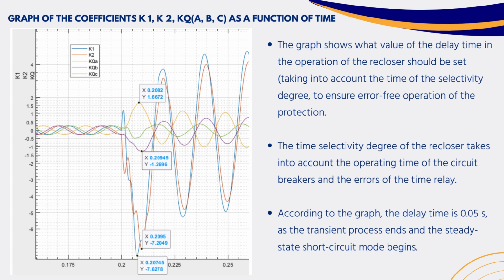And also in the next slide we see how it works, because all these results are modeling and simulation, not a real grid but a simulated grid in MATLAB, simulated in Simulink, but using real distances, real locations, and so on. These graphs show what value of the delay time in the operation of the reclosers should be set, taking into account the time selectivity degree to ensure error-free operation of the protection. The time selectivity degree of the reclosers takes into account the operating time of the circuit breakers and the error of the time relays. According to the graph, the delay time in our case is 0.05 seconds, when the transient process ends and the steady state short circuit mode begins.